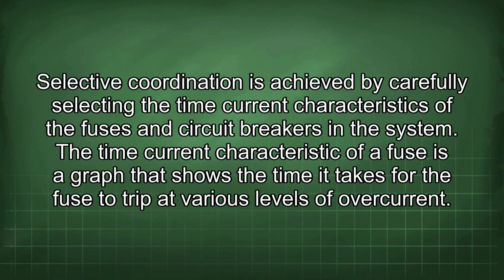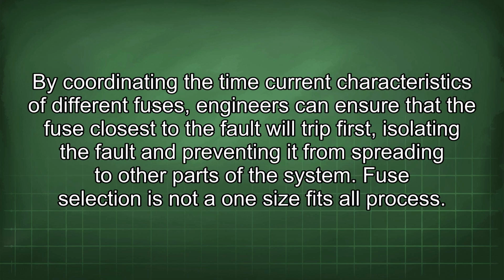Selective coordination is achieved by carefully selecting the time current characteristics of the fuses and circuit breakers in the system. The time current characteristic of a fuse is a graph that shows the time it takes for the fuse to trip at various levels of overcurrent. By coordinating the time current characteristics of different fuses, engineers can ensure that the fuse closest to the fault will trip first, isolating the fault and preventing it from spreading to other parts of the system.